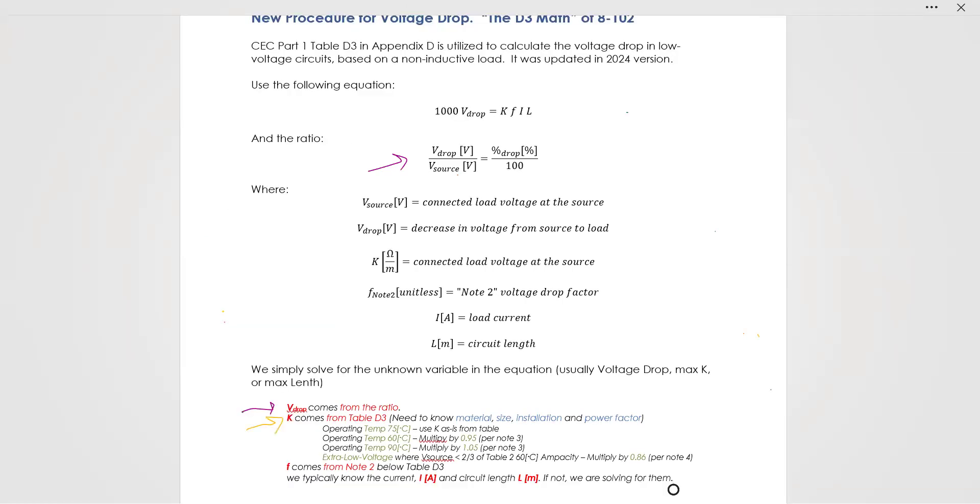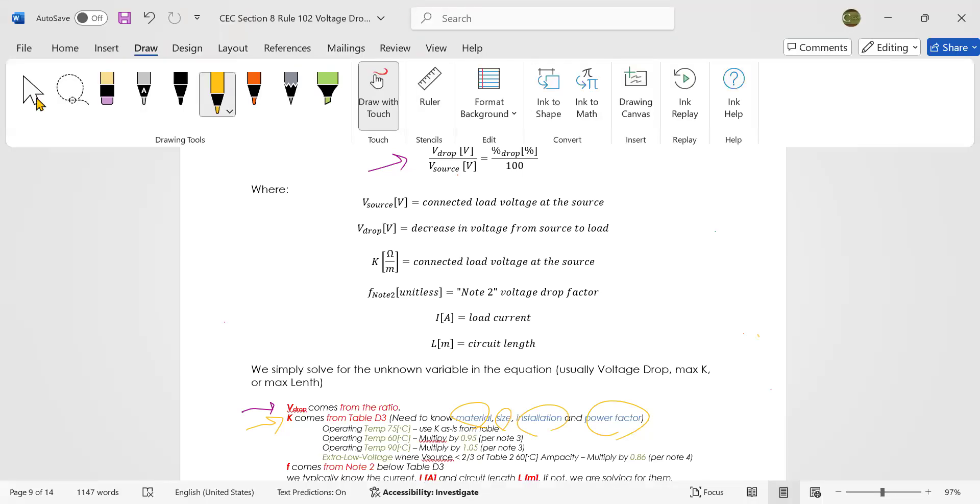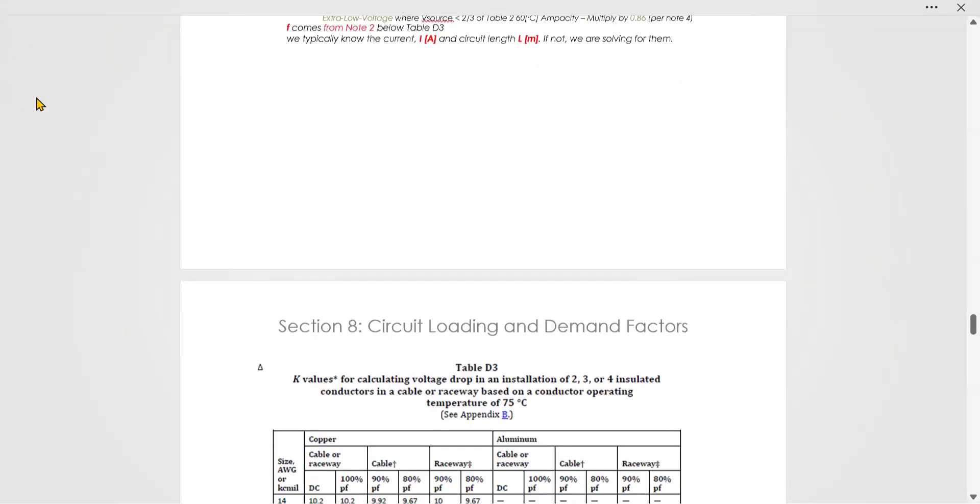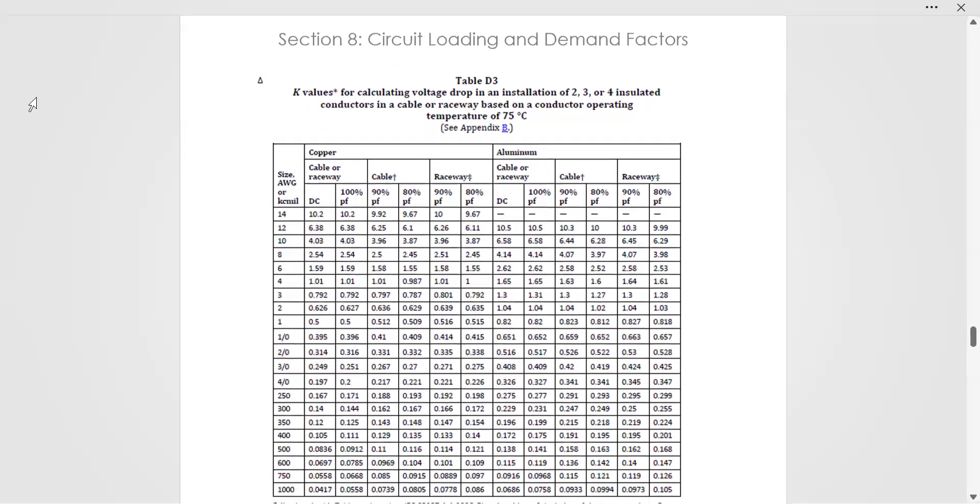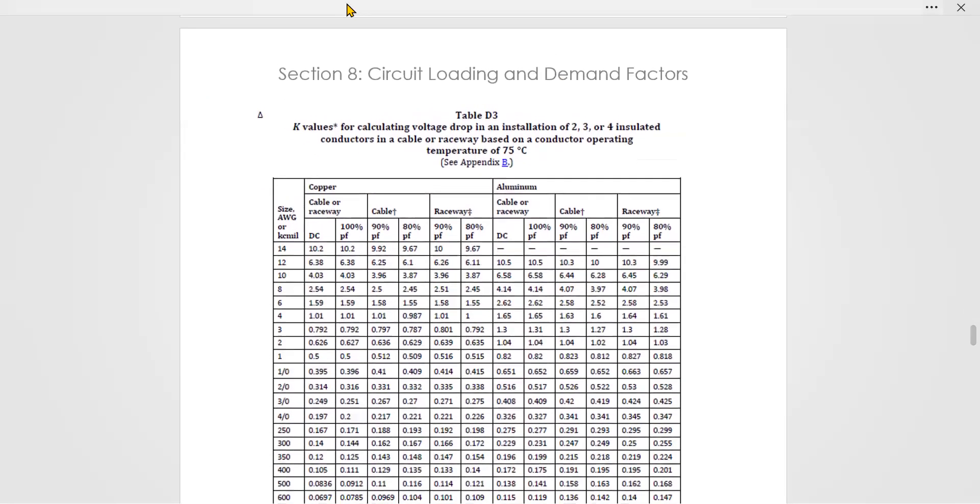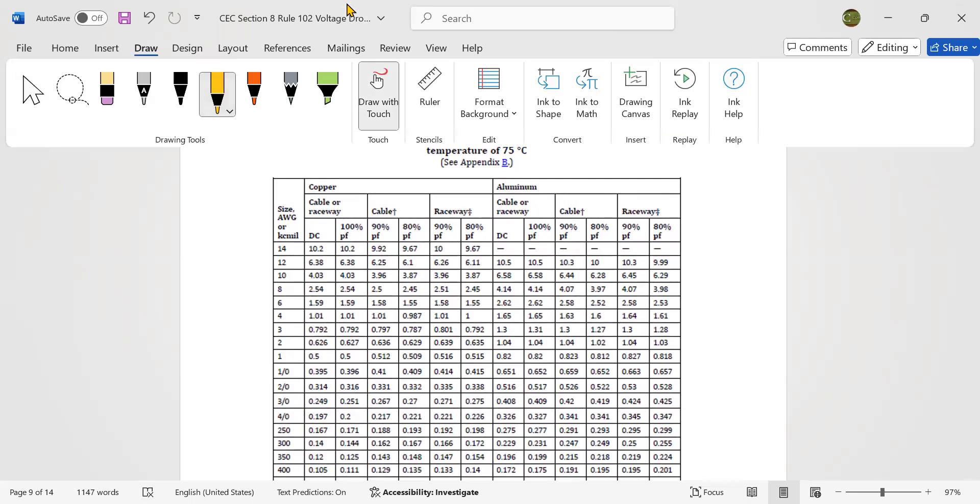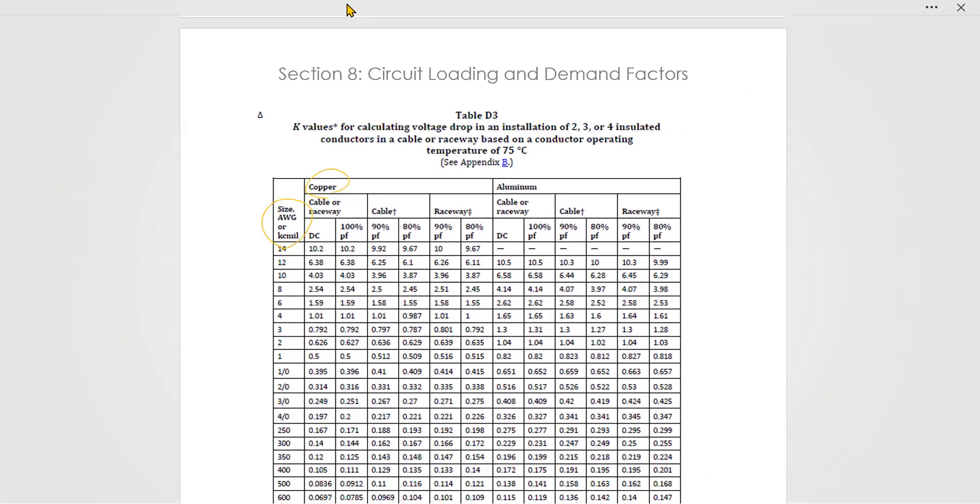K comes from table D3. In order to know K, we need to know the material, the size, the installation, and the power factor. Let me scroll down to table D3 and show you what I mean. We have to know the size, the material - copper or aluminum - the installation, and the power factor. That's all it is for table D3.